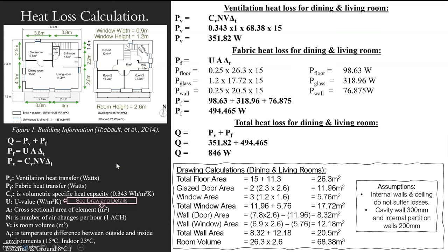You can get the U-value by doing a calculation — you need to see a previous video about that. However, once you have those U-values, that's fairly simple as long as you've got them for each element. For each element, you need to know the cross-sectional area, because your U-value is how quickly heat moves through that material, but you also need to know how much of that material it's going to move through.